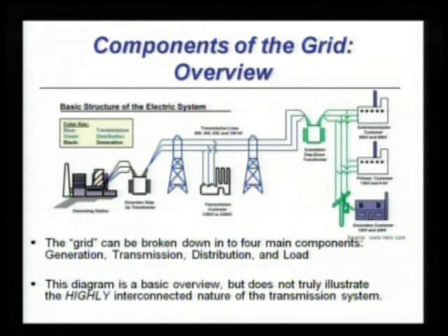Our grid is composed of basically four main components. You start with the source, which is the generating station. You go through transformation to the transmission grid — typically anything 100 kV and above. Standard voltages will range in the U.S. depending on standards local utilities have adopted, but typically 138, 230, 345, and 500 kV are standard. Then there's a distribution system meant to directly serve customers, including larger industrial customers. They may connect directly to higher voltages, but household secondary customers running off 120 or 240 volts nominally will be connected to slightly lower voltages.